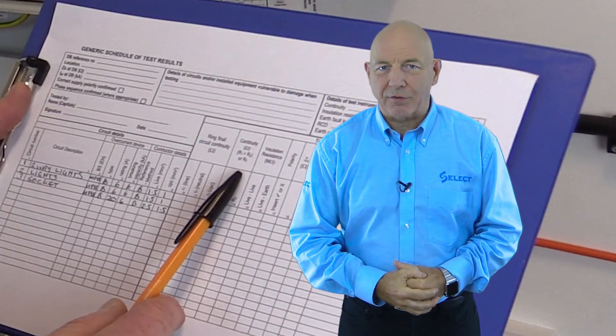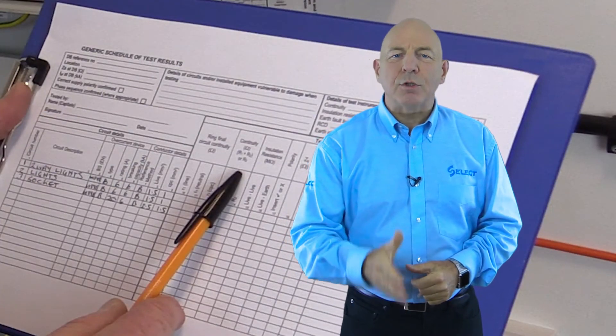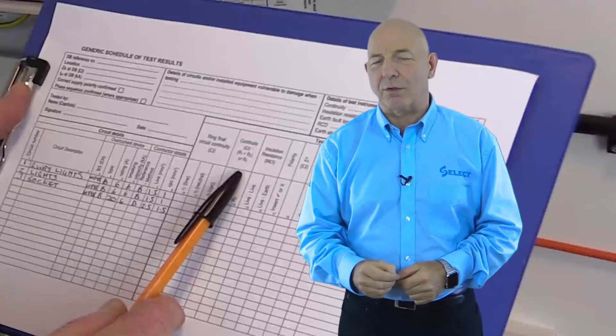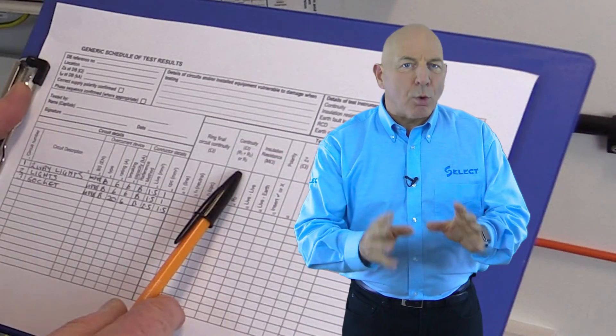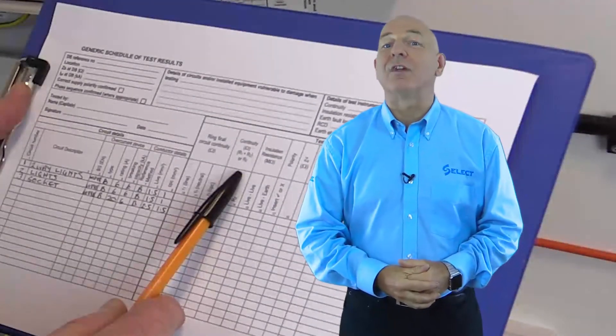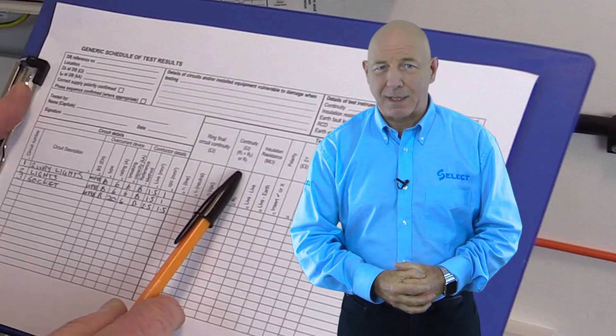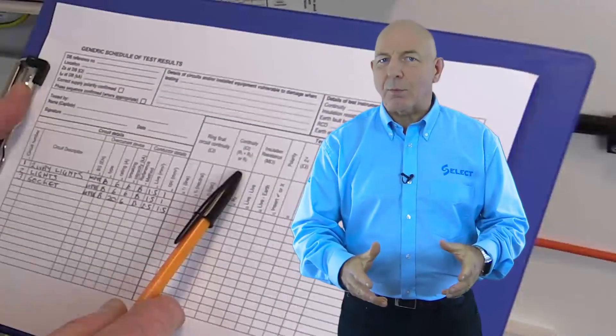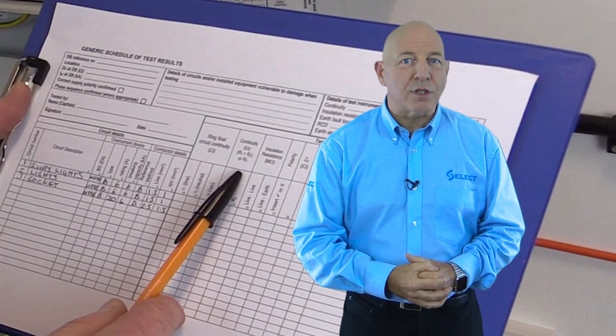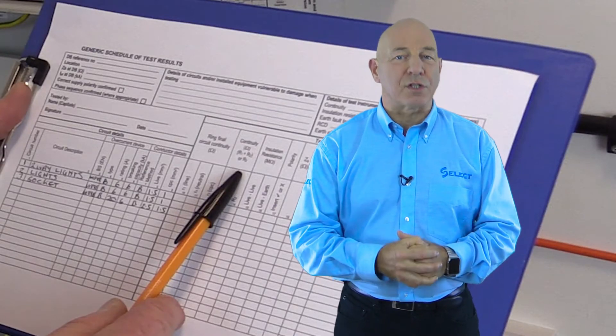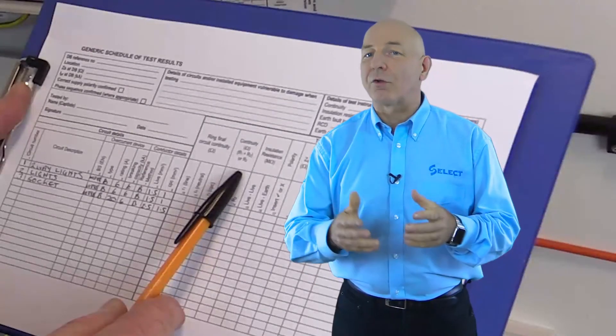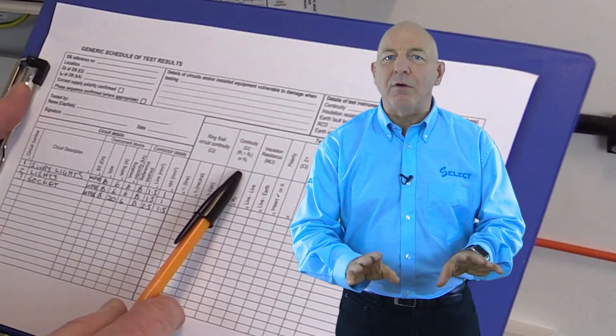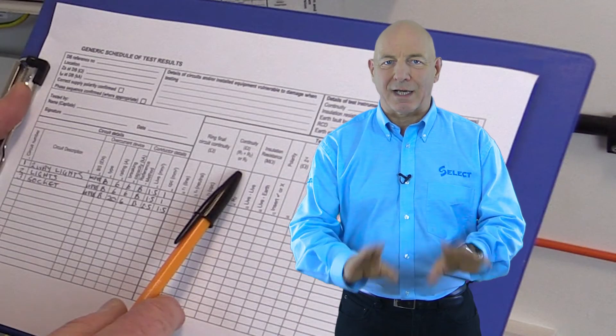After completion of each test, the measurement should be recorded in the relevant column of the schedule of test results. A model schedule of test results is given in Appendix 6 of BS 7671. The inspector will then need to use his or her knowledge to compare the results obtained against certain criteria given in BS 7671 to verify that the outcome is satisfactory.